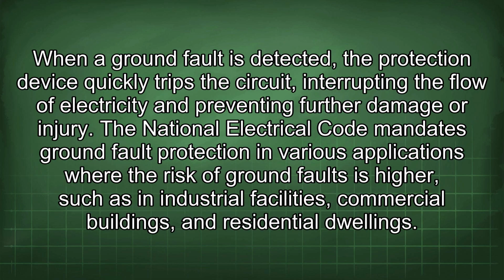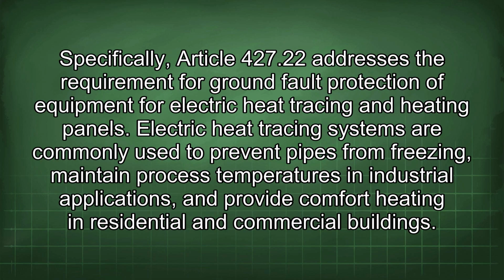When a ground fault is detected, the protection device quickly trips the circuit, interrupting the flow of electricity and preventing further damage or injury. The National Electrical Code mandates ground fault protection in various applications where the risk of ground faults is higher, such as in industrial facilities, commercial buildings, and residential dwellings. Specifically, Article 427.22 addresses the requirement for ground fault protection of equipment for electric heat tracing and heating panels.